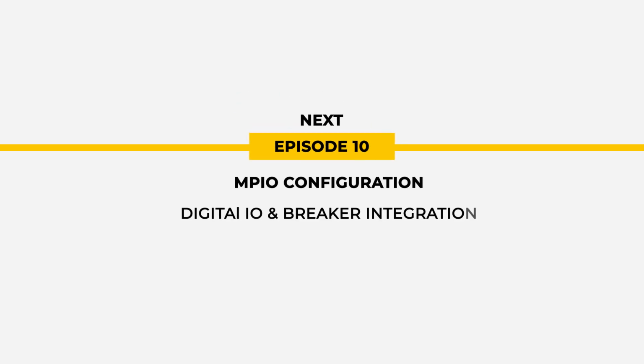That's how you configure Genset meters in Econ, defining how the EMS detects and monitors each generator based on power or frequency inputs. With these settings, the system accurately tracks generator activity and power contribution. In the next episode, we'll configure multi-purpose I/O modules to interface with breakers and site protection systems.